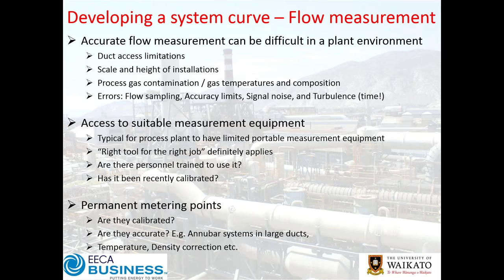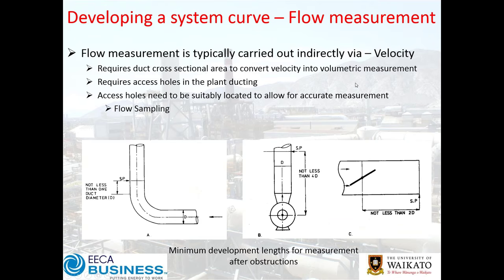Permanent metering points are another option — are they calibrated and accurate? Annubar systems in large ducts are a good example: if duct flow isn't uniform, are they located in a good spot? Flow meters also require density, temperature, and pressure corrections. Flow measurement is typically done via velocity, requiring a cross-sectional area for volumetric conversion. Access holes need to be in appropriate places — generally at least one to a few duct diameters from bends, transitions, dampers, and valves.